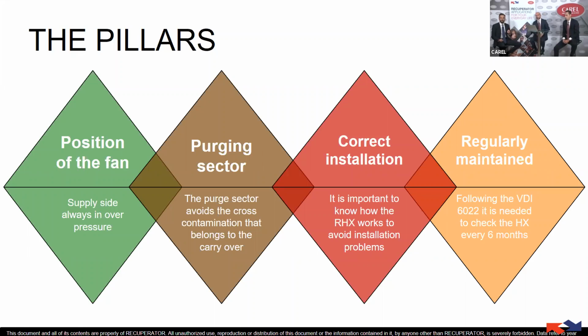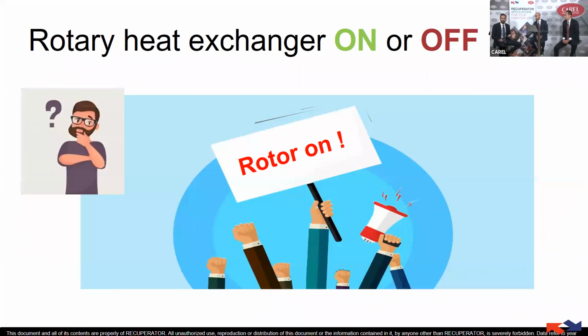Following these 4 pillars, it is not needed at all to switch off the rotor. Actually, it's really important, because it's been shown that if these 4 pillars are fulfilled, there is no evidence of a transfer of virus-laden particles higher than 0.2 microns. And we've also seen that the leakage does not depend on the revolutions per minute. So if we stop the wheel, we just stop the carryover that can already be avoided with the purging sector. In addition, if we switch off the rotor, we can have an increase of energy consumption, and we can have discomfort inside that can increase, we hope not, the spreading of the virus. So it's really important to follow the 4 pillars and not be afraid to use the rotary heat exchanger, because with those 4 milestones we can use it in a proper and safe way.